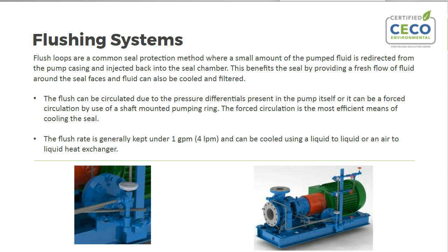Another way that we protect the seal is through flushing systems. Most of these systems were developed by API, the American Petroleum Institute. They basically use a circulating fluid that does a number of different things. Flushing the seal is a common way to keep fresh fluid around the seal. It's a common way to keep solids from building up at the seal faces, and it's a common way of getting more reliability and longevity out of the seal. But that flush fluid, in high temperature applications, can also be cooled. It can also be filtered in some cases.